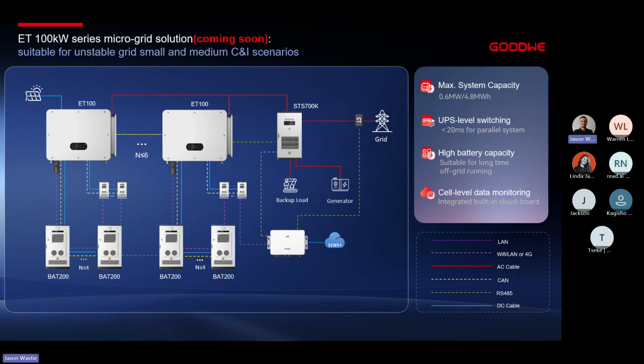So all of our inverters will connect together to one common STS, and that common STS will then be able to distribute the power to our backup loads, as well as receiving the power from the grid or our generator, or if there is no generator, to a secondary AC output as we may require.